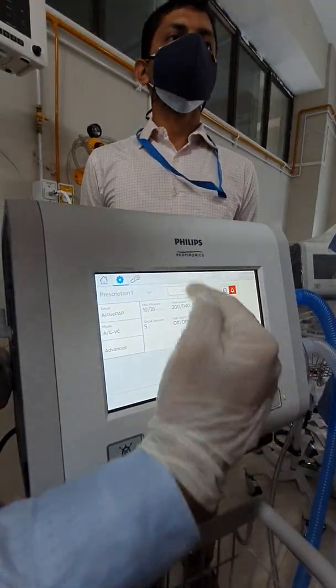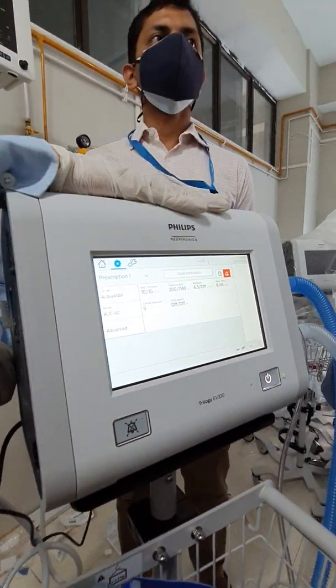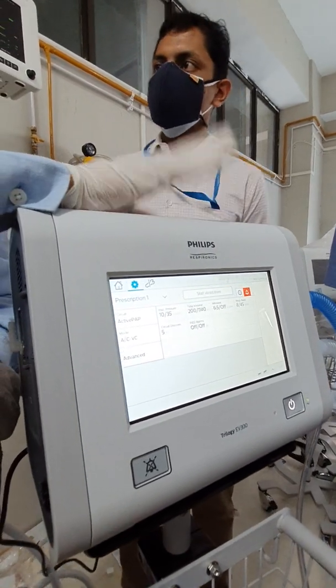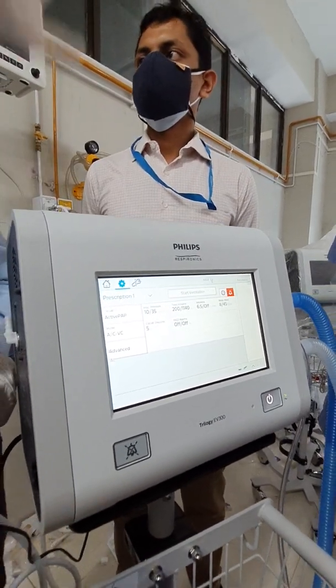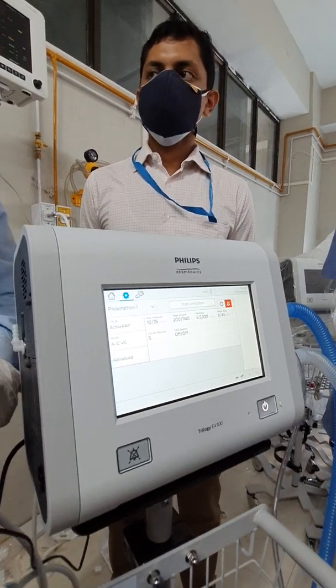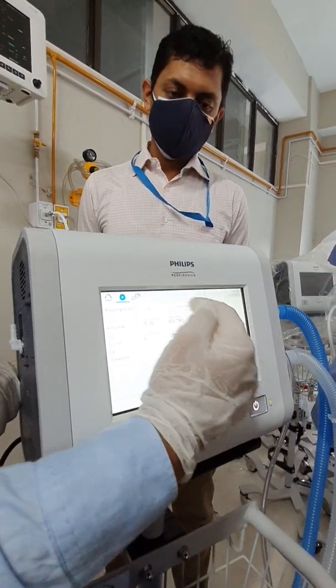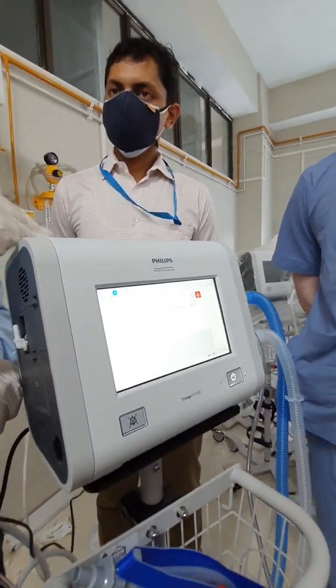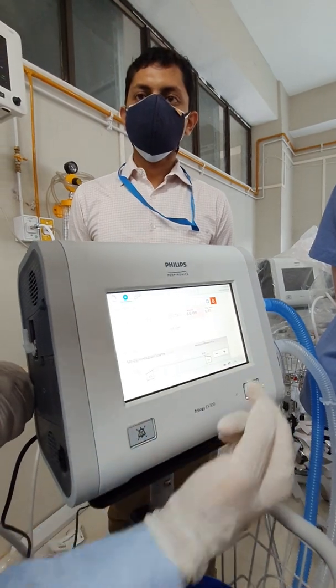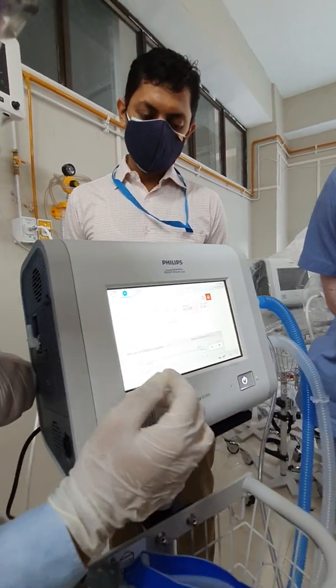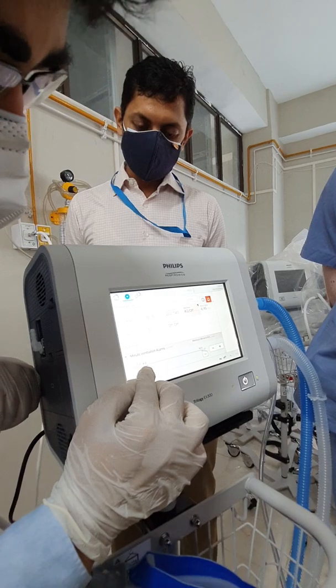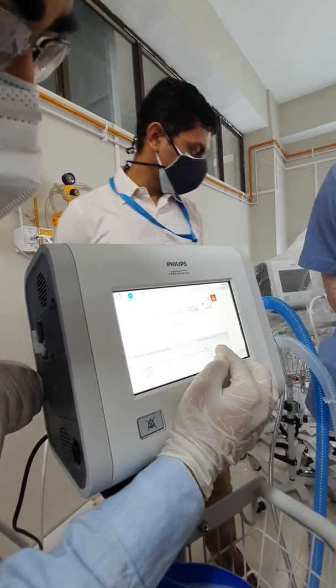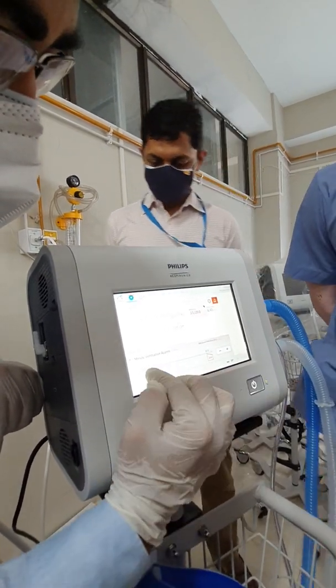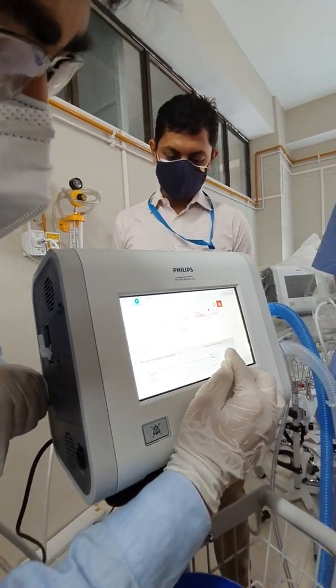We change the alarm on the minute ventilation. This alarm is the most frequently occurring alarm among the ventilators. Why? Because we don't look at the alarm setting. See, 6.5. What is the normal minute ventilation? It is 6 to 8. So if you don't change it, it is going to alarm. So it should be like 3. Upper limit. Okay.